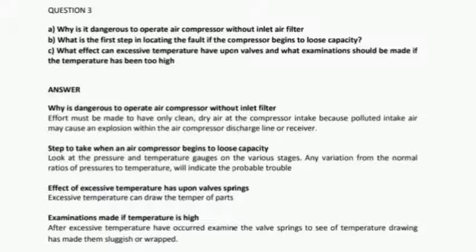They may stick to valves and make them not close properly. This may lead to higher discharge temperatures and formation of carbon deposit. The carbon deposit could become so hot on valves that are not closing properly and act as igniting points for the air and oil vapor mixture, thereby leading to possible fires or explosions in the compressor.